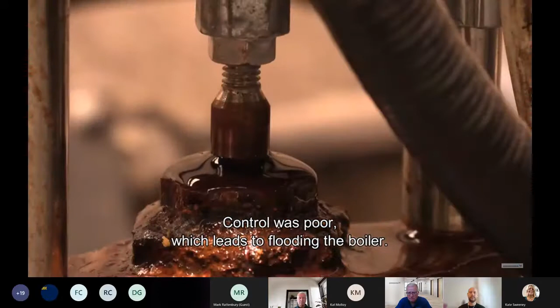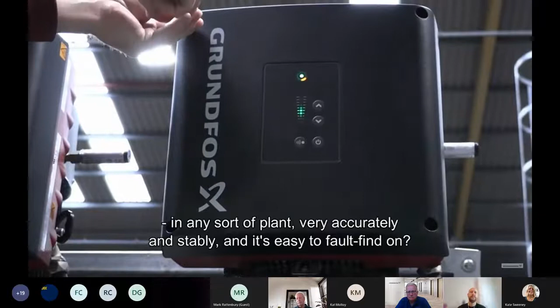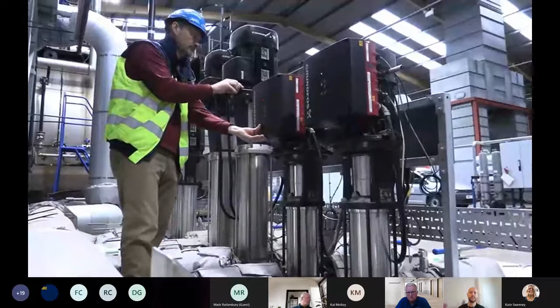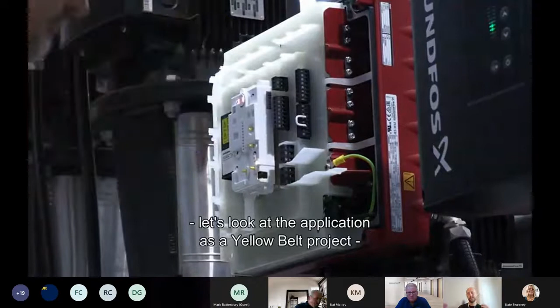After going down and meeting one of the Grundfos away days to look at the products, I bumped into Soren and he showed me a demonstration of what I thought was just continuous control for any sort of application. We used them right across site, but when he told me it was for a boiler, that was a light bulb moment for me. I'd always wondered why we had this static control with a feed water valve on boilers, when with modern technology we have a 4-20 output running a variable speed drive which will control any level in any plant very accurately, very stably, and it's so easy to fault find on.